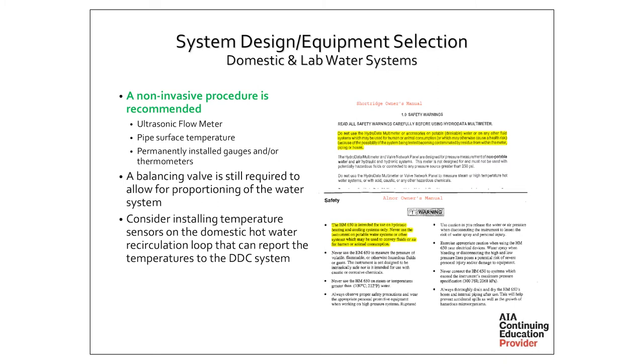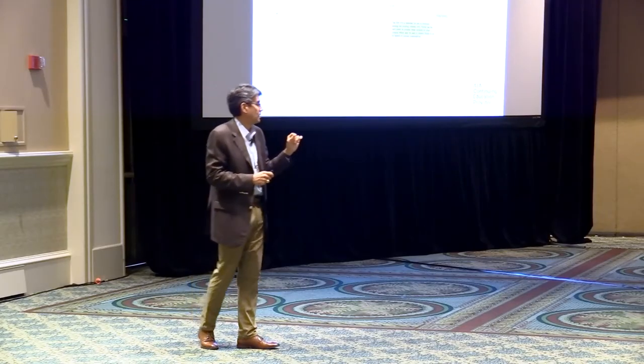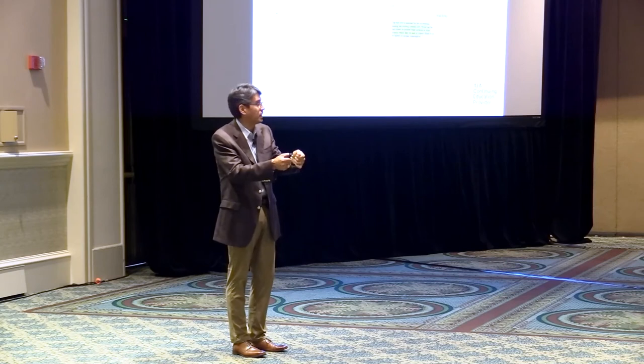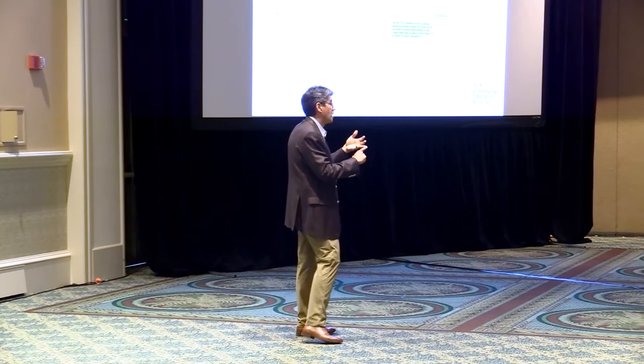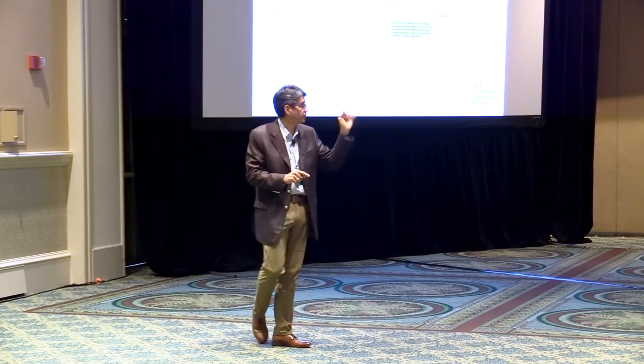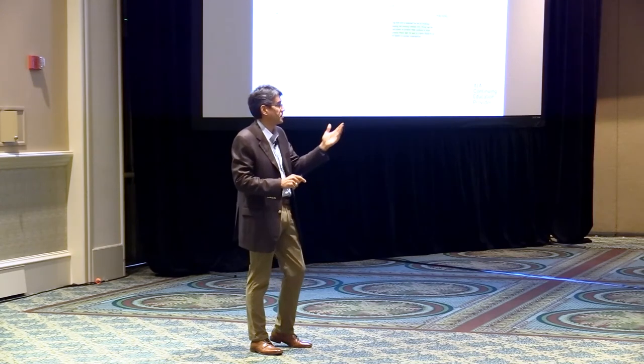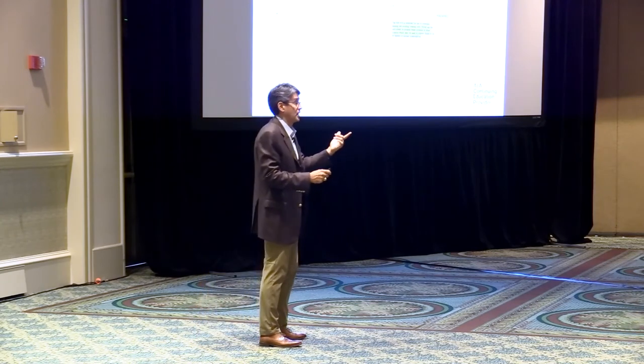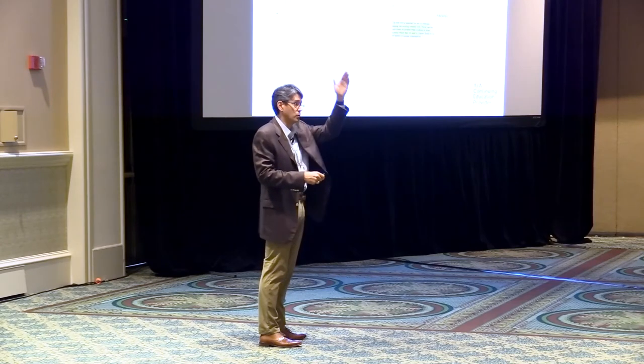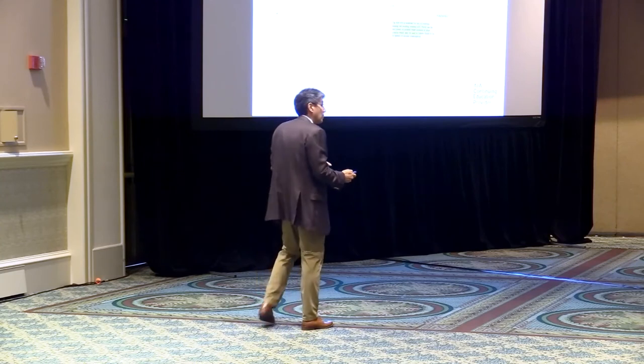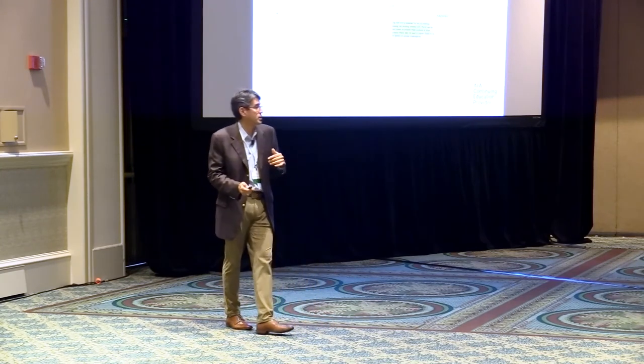For domestic water systems: TAB instrumentation per TAB manuals — Alnor, Short Ridge — is not rated for potable water use, so you don't want the TAB technician inserting instruments into potable water. Use non-invasive methods: ultrasonic flow meters, temperature sensors. For a large hot water recirculation system, put temperature sensors on DDC off each main branch to verify you're getting 120°F — the maintenance staff loves it because they can quickly confirm the system is working.